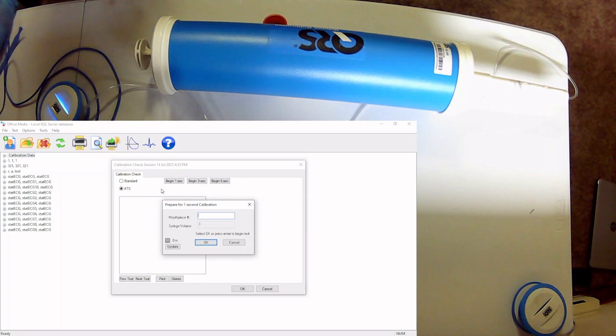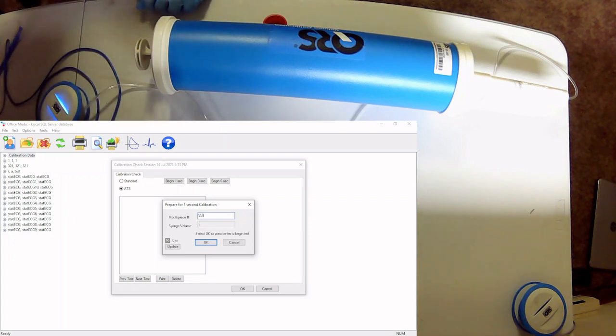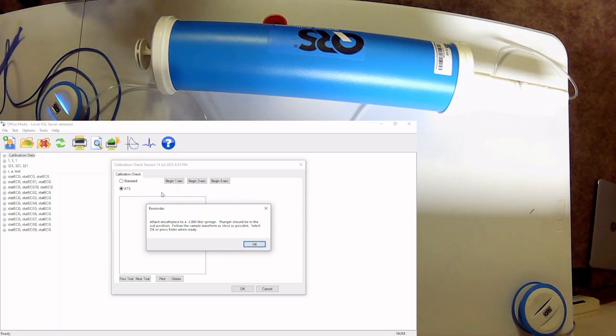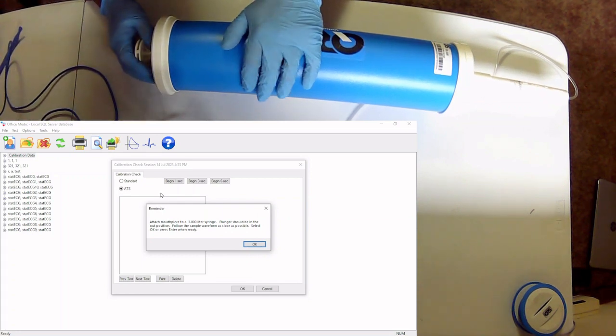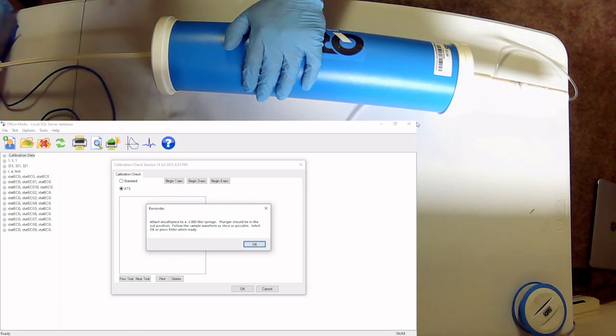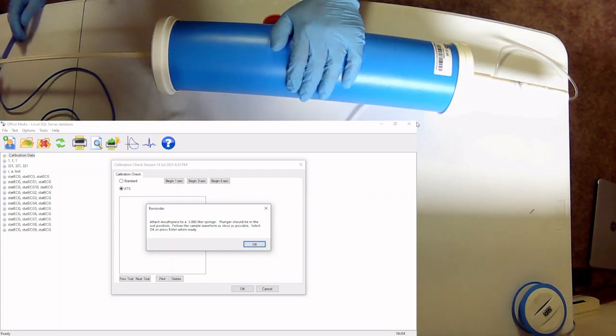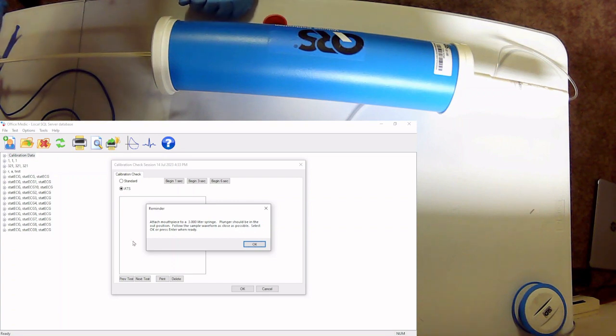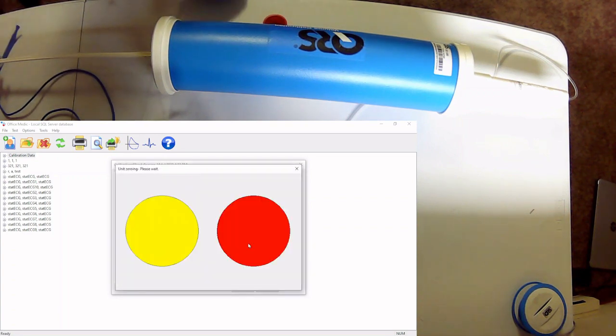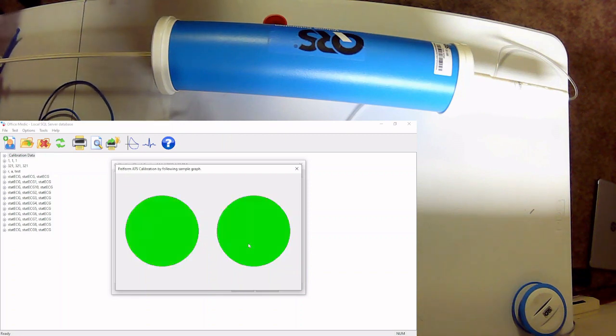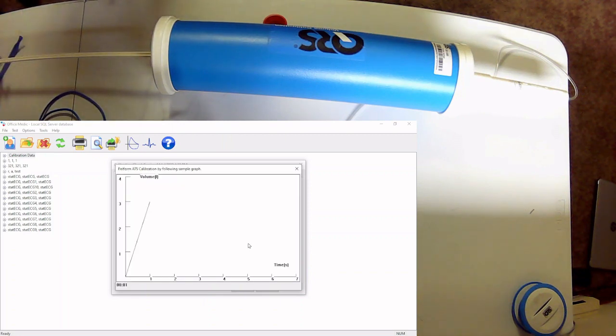I'm going to start with the 1 second test. It's going to prompt us for the mouthpiece number. And I'm going to go ahead and enter that in. 585. Click on OK. Now it's going to give us a notification that we need to have the plunger extended all the way out. I'm going to pull it out until you hear that little click. That means it's ready to go. Click on OK. And we're going to wait until the device finds 0 pressure at the mouthpiece. And that double green symbols or circles means that it's ready to go.